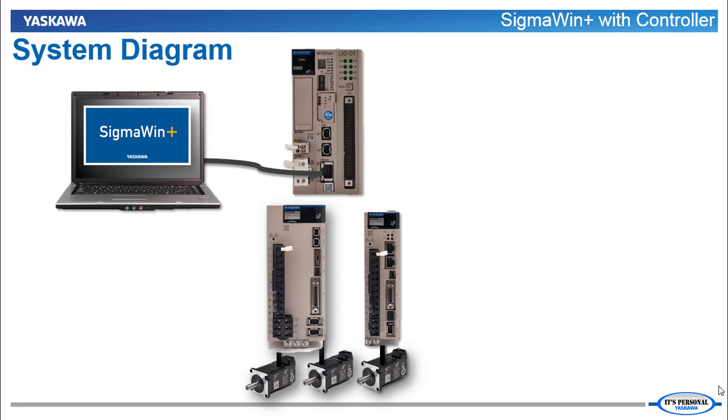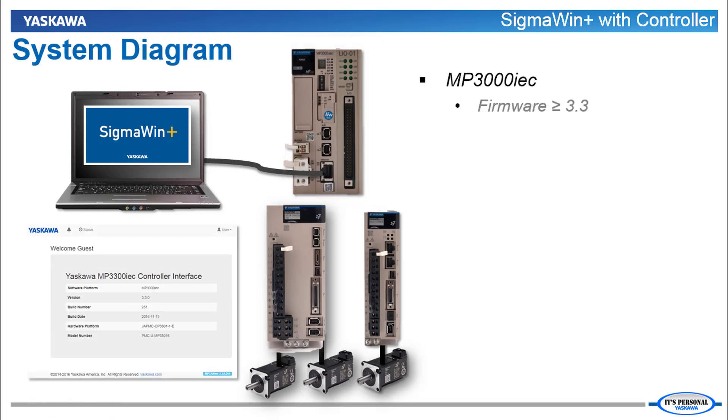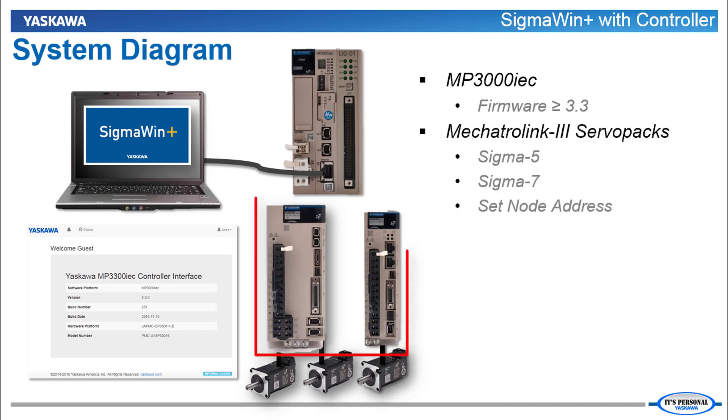Communication of Sigma Win Plus through the controller requires an MP3300 IEC or MP3200 IEC controller with firmware level 3.3 or greater. This feature is not affected by the version of MotionWorks IEC. Mechatrolink 3 servo packs are also required, either Sigma 5 or Sigma 7.